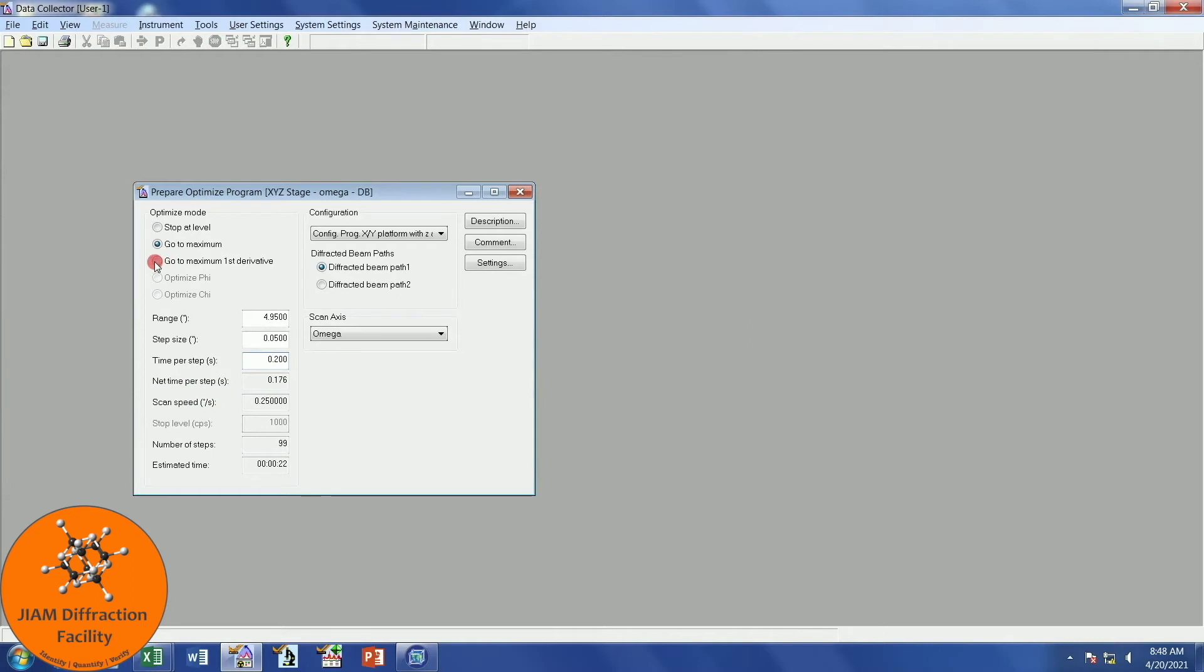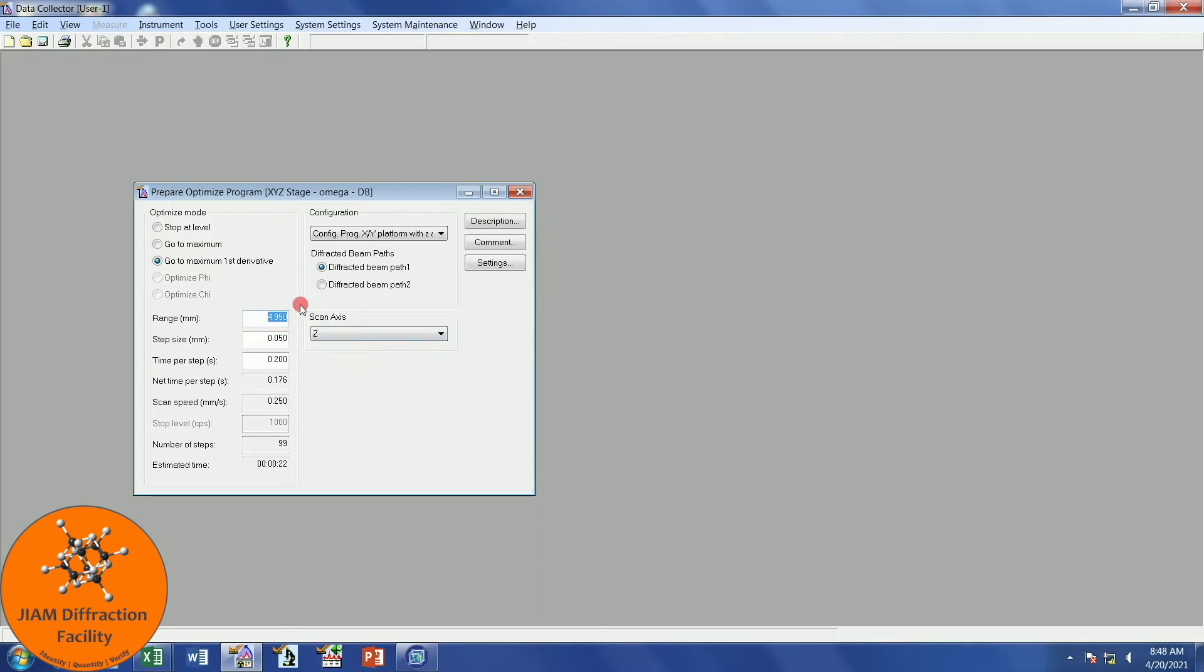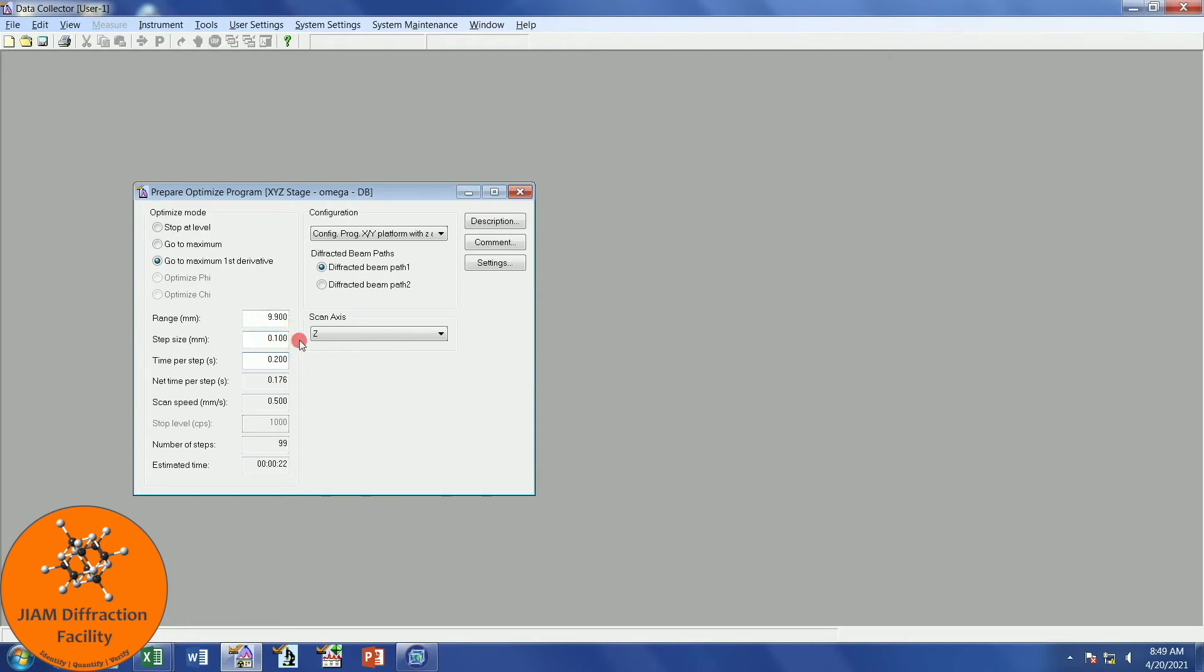Now we want to change this to go to maximum first derivative. That means that it will scan the axis, it will find the derivative of the curve, and it will move the axis position to match up with the maximum point on the first derivative curve. For this, we want our scan axis to be z. Again, because we have a wide variety of samples entering the lab, they will all have different thicknesses, so to capture the feature that we want to capture in this scan, I need to first have this be a pretty large range. So I will set this up to be 10 millimeters, which makes the step size 0.1 millimeters. Time per step still remains the same. Again, if you have the same type of sample that is always the same height, then you might be able to set this up to be just 1, and then your step size to be 0.01. But I like to set a large range to begin with.